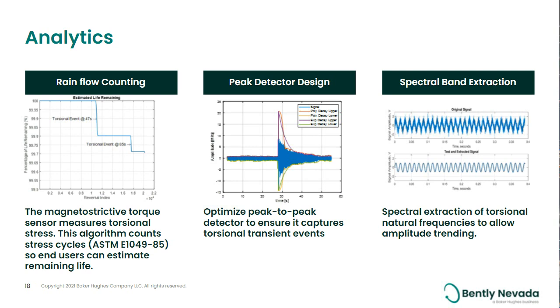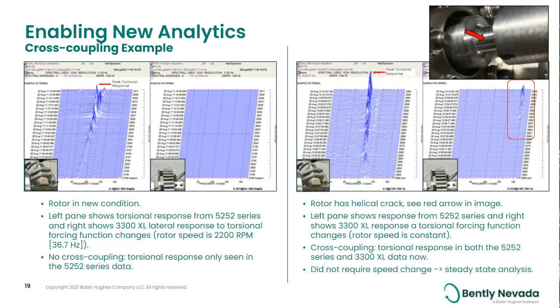We want to conclude with some thoughts on how torsional vibration further enhances machinery diagnostic capability. This slide shows data taken from a test kit instrumented with the 5252 series probes, left plot on both sides, and eddy current lateral vibration probes, right plot on both sides. The left side of the slide shows data taken with the shaft in new condition. The left pane on this side shows the 5252 series response as the torsional perturbator is swept through the resonant frequency. This frequency sweep results in the peak shown in the left plot.